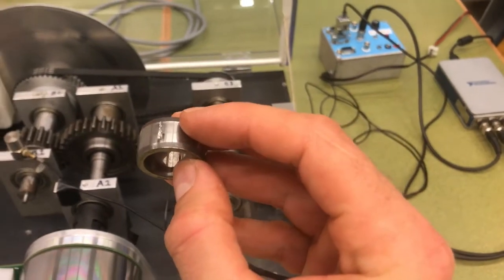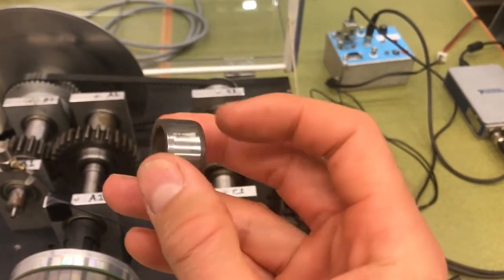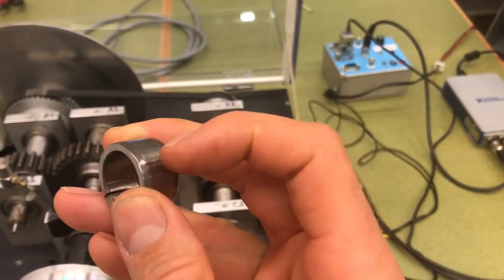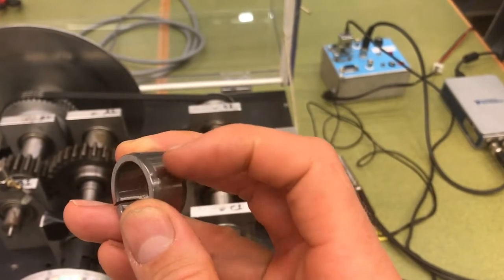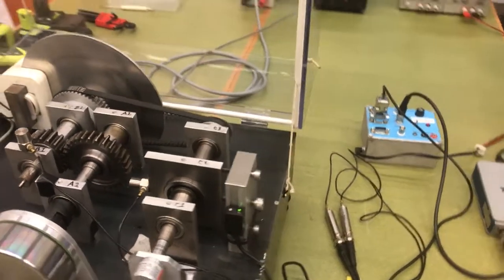So if I can just get the camera to focus, you can hopefully see that this has got a mark in here where that bearing surface has been scored. And as the rolling elements pass over this, then clearly they will introduce a cyclical amount of load.